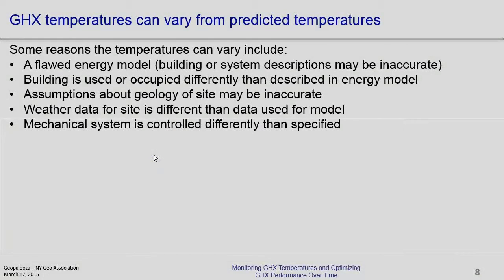There's a couple of reasons that the temperatures would vary from that. One is the building energy model might be flawed to start with. Maybe you got a poor description from the architect or the builder or the owner, or the building is being used or occupied differently than you were told by the owner, or the way you described it in the energy model was wrong. And then the assumptions of the geology of the site, you may be wrong. You may not have realized that there was good water flow through that ground, or you thought there was groundwater flow and there wasn't. So your assumptions may have been wrong. The weather data for the site is different than the data used for the model, and in mountainous areas, that can be fairly tricky. And then the mechanical system is being controlled differently than you've specified.